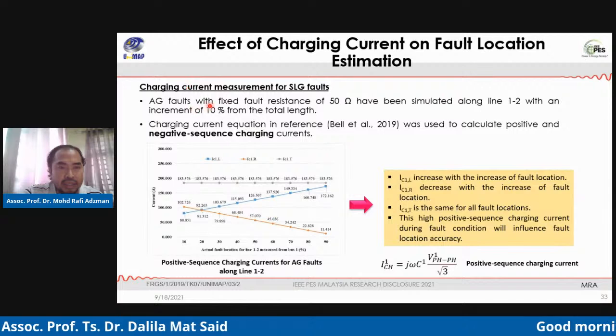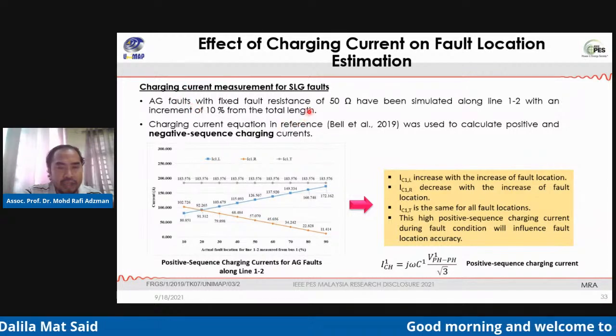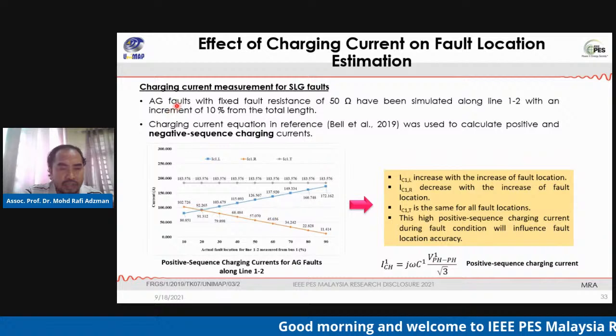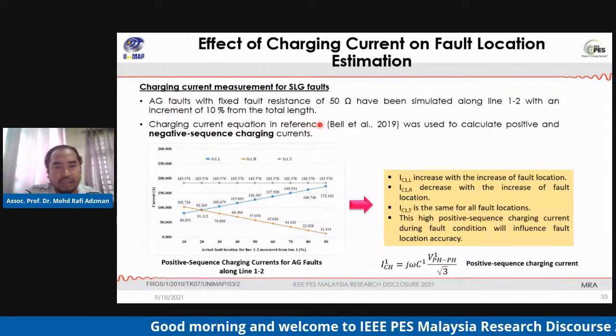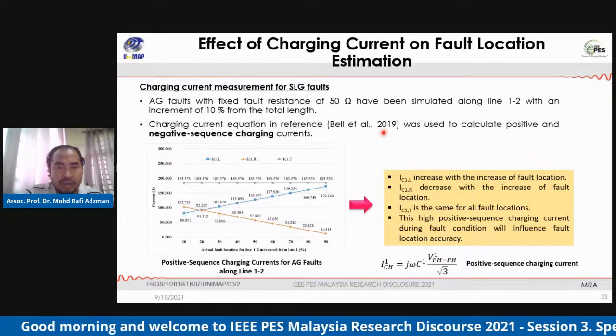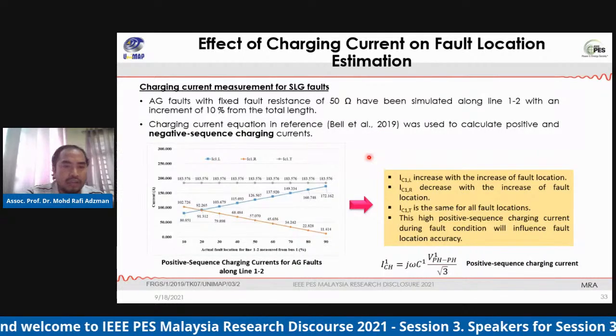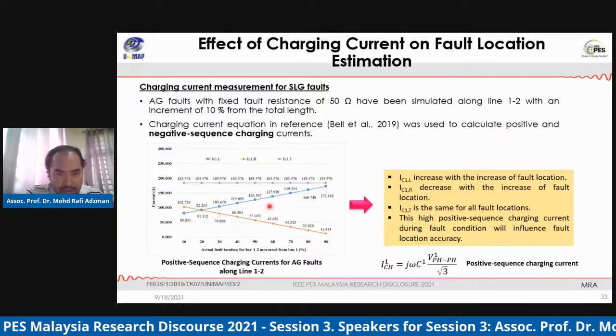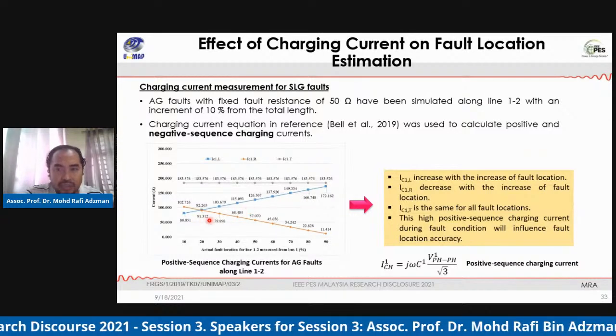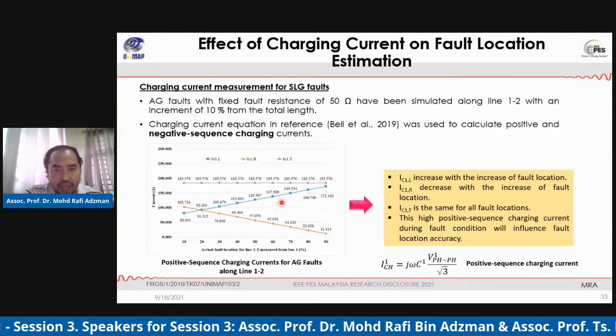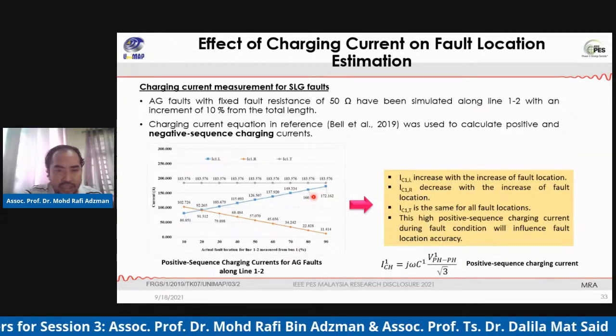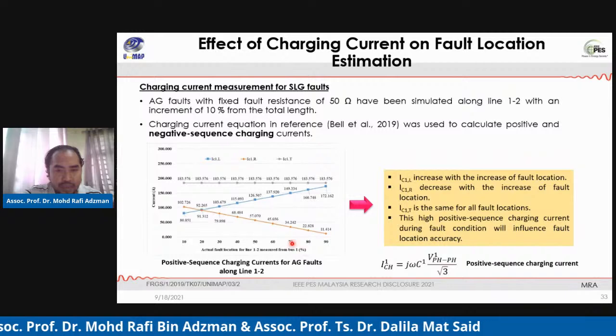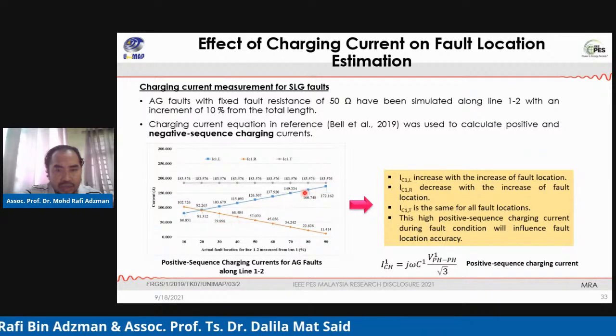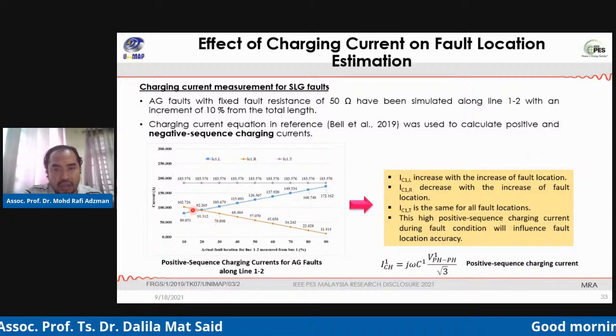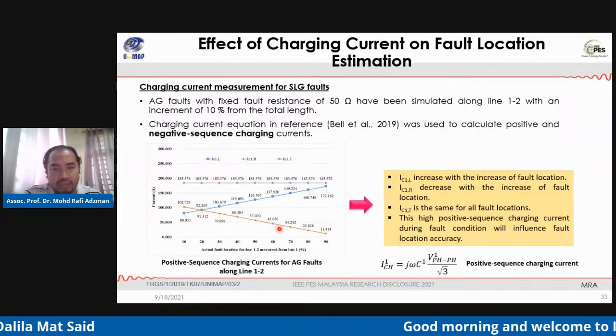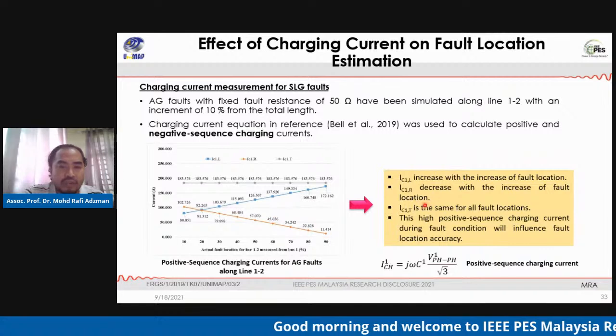So let's see the charging current that we measured during single line to ground faults. For the AG fault with a fixed fault resistance of 50 ohms, we used it along line 1-2, with increments of 10% of the total length. Here we can see that the positive sequence charging current measured from the local end increases with the increase of the fault location, and the positive sequence charging current measured from the remote end decreases with the increase of the fault location.